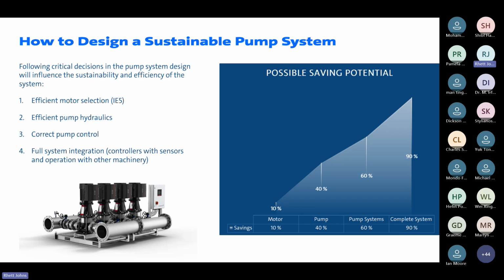Really, it's covered by 4 steps, and you can think of it as starting small and working bigger and bigger. Working outwards from the pump, you can start saving more and more energy in your system. The first one is selecting and using an IE5 motor, and preferably integrated motors with integrated VSDs, which will allow for a 10 to sometimes 20% reduction in energy depending on the size of the motor. When we talk about efficient pump hydraulics, we're talking about correctly sized pumps running in the correct area of the curve, and we'll explain that a little bit later. That's going to increase your potential savings up to 40% on your system.